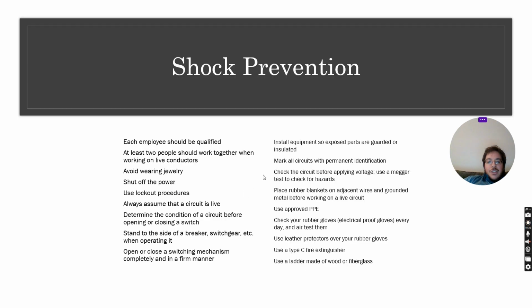So how do we stop people from getting shocked? Well, we can't, but there's a number of ways. So first of all, everybody that's working should be qualified, and if we have to, we should try to not work on live circuits wherever possible. So if you can shut off the power, but if you can't, then always assume the circuit's live, and always have at least two people working together. That way, if one of them gets hurt, the other one can get help for them. And then avoid wearing jewelry. Always stand to the side of a breaker when opening it. Make sure you close the switch completely and in a firm manner. That reduces the risk of an arc flash.